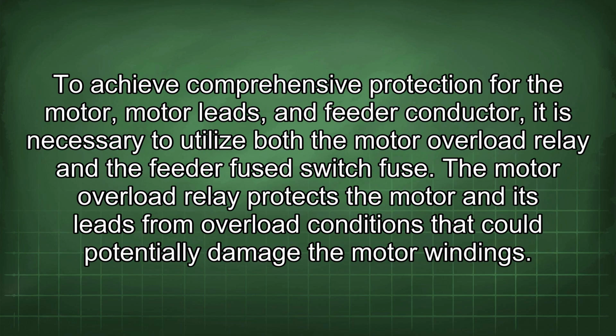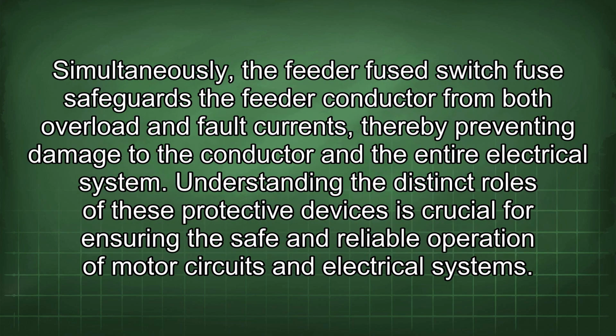To achieve comprehensive protection for the motor leads and feeder conductor, it is necessary to utilize both the motor overload relay and the feeder fuse switch fuse. The motor overload relay protects the motor and its leads from overload conditions that could potentially damage the motor windings. Simultaneously, the feeder fuse switch fuse safeguards the feeder conductor from both overload and fault currents, thereby preventing damage to the conductor and the entire electrical system. Understanding the distinct roles of these protective devices is crucial for ensuring the safe and reliable operation of motor circuits and electrical systems.